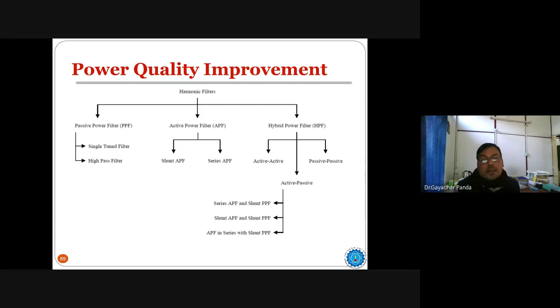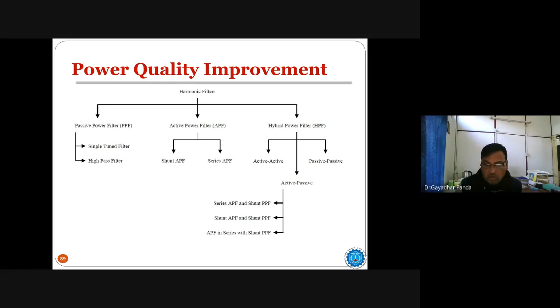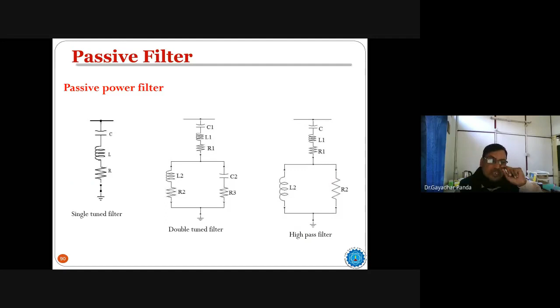Yes, we are interested a little bit here in the power quality improvement using different power filters, like the passive and the active power filters. There is also the combination of passive and active, that is the hybrid power filter. Particularly for passive filters, we know there is a major drawback: they can eliminate only particular harmonics, and they are bulky in size. Whereas the active power filter is dynamic in nature. Depending on your requirement, you use your control algorithm and produce the compensating current to compensate the harmonics. It is called the active power filter because an energy source is available where you can produce the compensating current, which is not possible with passive filters.